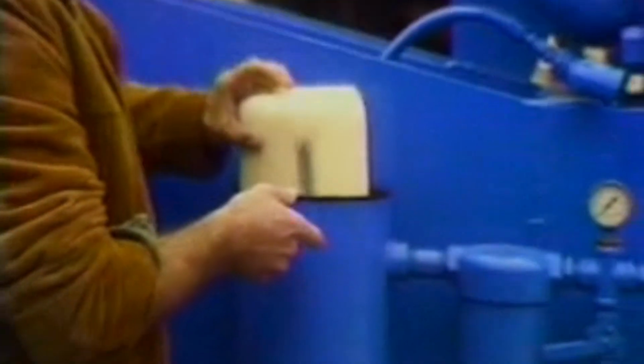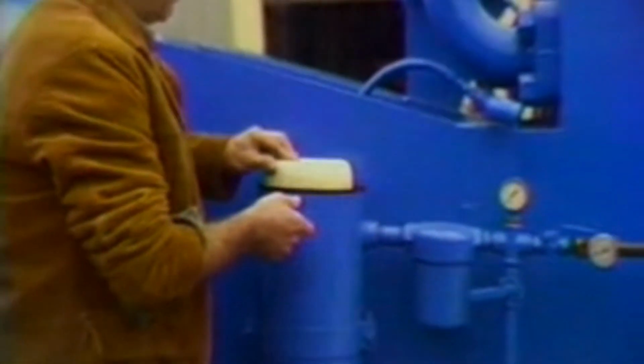Take a look at the element when you remove it. It can tell you what type of contaminants you may have in the oil, and it can also indicate whether the lubricant needs to be changed at this time. Be sure you clean the case of the filter before putting the new element in. You should plan to change the filter element every 2 or 3 weeks if your pump is operating continuously, but change it sooner if the pressure at the filter indicates the need.